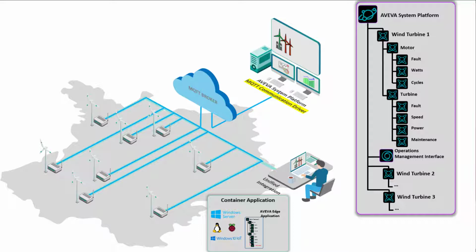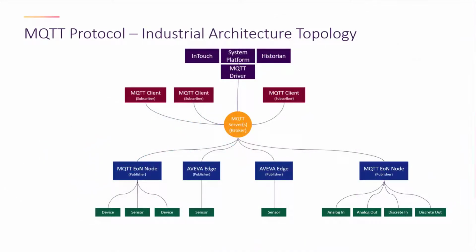So let's first break down the MQTT layer, the topology of an MQTT network. At the bottom, the first thing that you would have is the devices. Traditionally, in our industry, not everything is automated to natively speak MQTT protocol. If I haven't said it before, MQTT stands for Message Queue Telemetry Transport, a very lightweight mechanism of packaging data and sending it over. Now, the devices at the bottom can be anything from, let's say, transmitters, thermocouples, motor controls, motor states, but again, as I mentioned, they're typically not connected directly to an IoT network. So how do we deal with that?